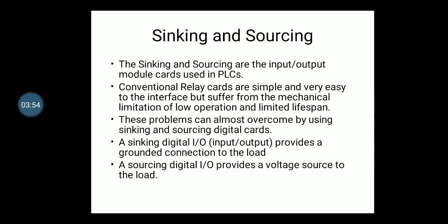By using this technique, we can overcome the problems which were in the relays, right? A sinking digital input output provides a grounded connection to the load, and a sourcing digital input output provides a voltage source to the load, right? So this is the only difference. Sinking digital is connected to ground, and sourcing is connected to the voltage, right?